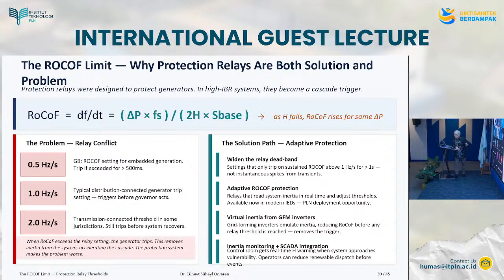And then there is 1 Hz per second, typical distribution connected generator trip settings, and that triggers before governors react, and 2 Hz per second trips transmission connected threshold in some areas, still trips before the system recovers. Now when rate of change of frequency exceeds the relay settings, the generator trips, removing inertia from the system, accelerating the cascade.